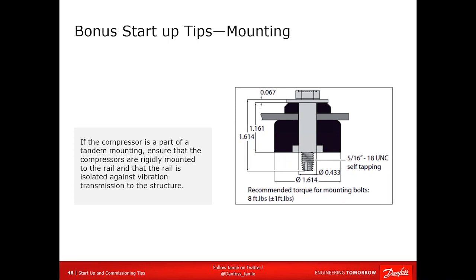So untorque them and torque them to what the manufacturer recommends so that the rubber grommet can float the compressor. And remember, if you have a tandem system, two compressors sitting on a rail, they are linked together and share a common suction and discharge.